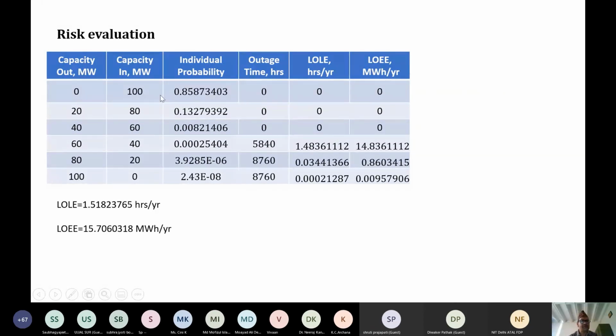So when 20 megawatt is outage, we still have 80 megawatt available with this probability. Outage time is 0, means all the load will still continue to get supply. So therefore, this outage time, meaning outage time for the loads, is 0 hours. All these things are also 0. In the third state, when 40 megawatt was outage, we still have 60 megawatt available with this probability. So our load is also 60 megawatt. So still the load is fulfilled. So no outage occurs.